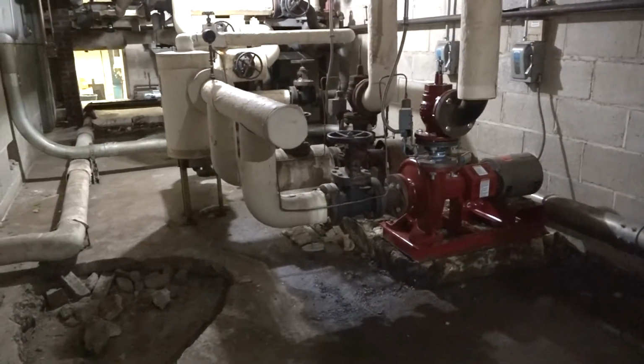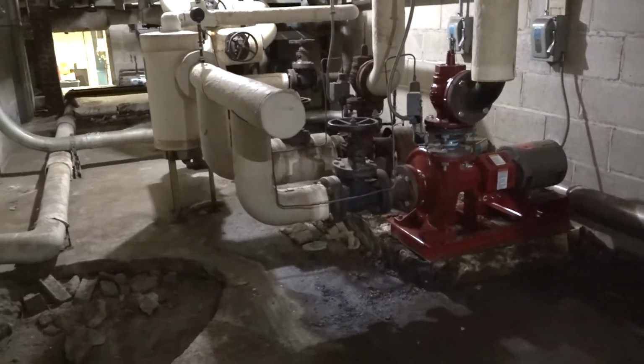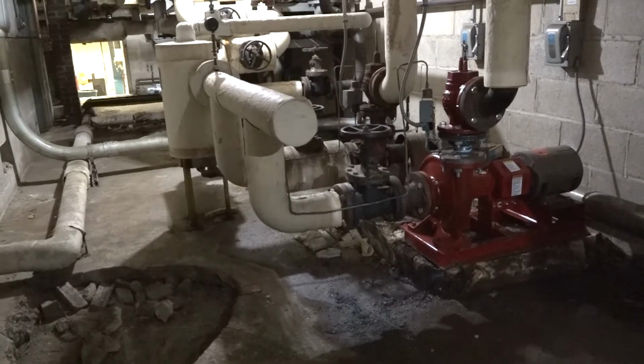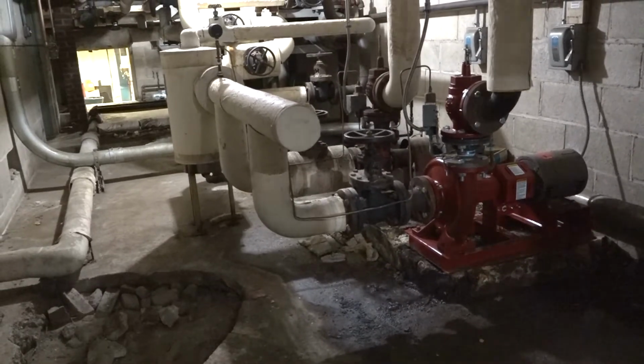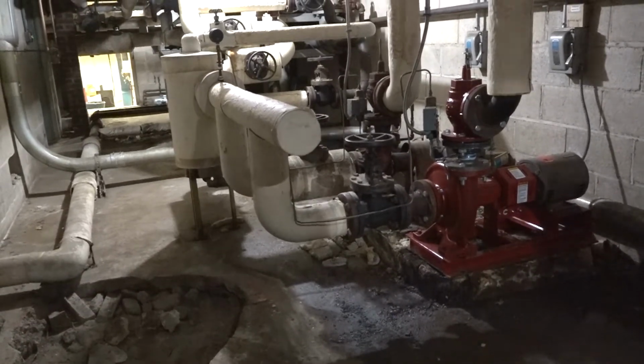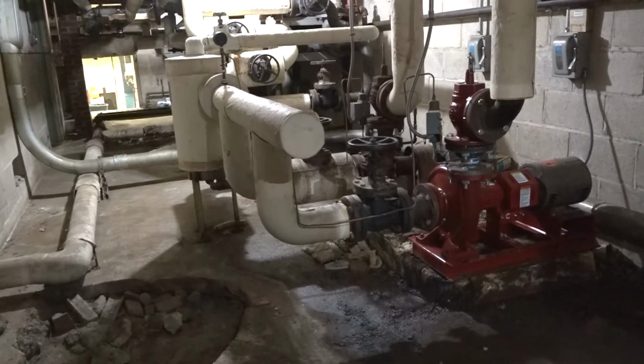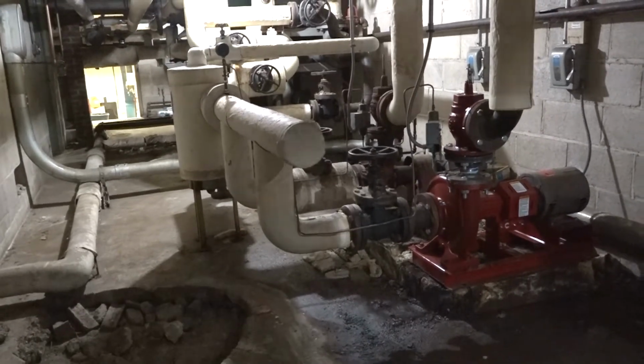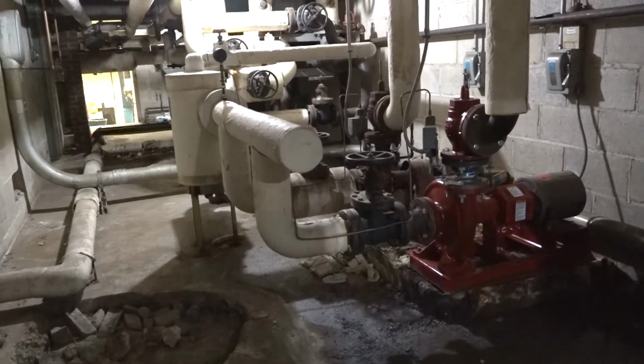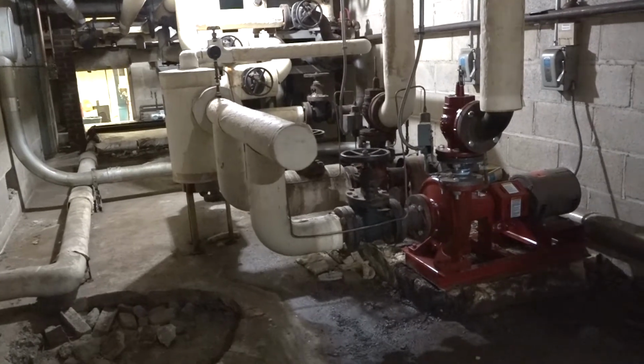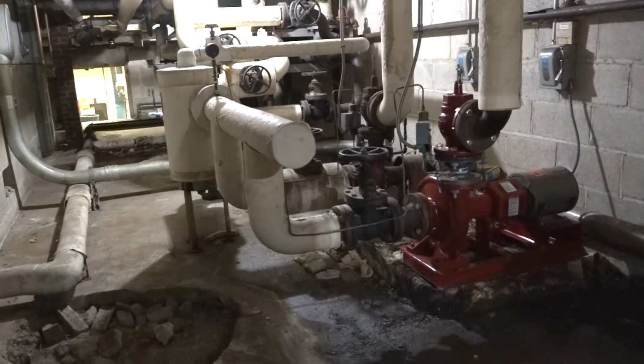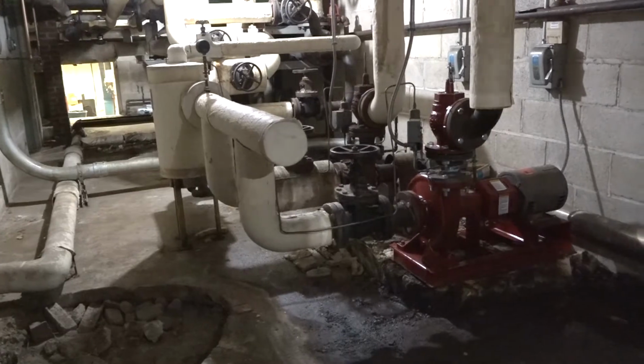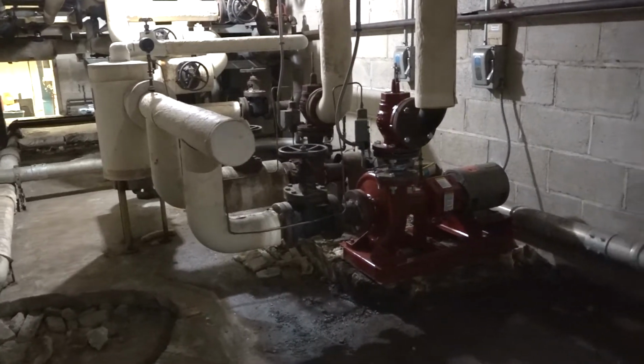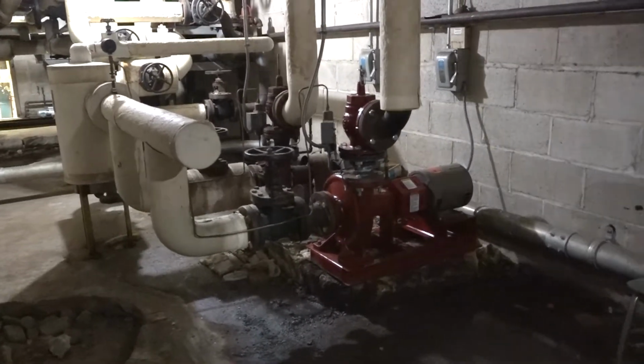So these are the circ pumps that come off of the heat exchanger, which is behind all the piping over there. The steam comes up in the heat exchanger, converts the steam into hot water through a city water feed, and then these pumps pump it through to the newer additions in the building. We had one pump fail 2 years ago. We had to replace the whole thing, base and all. Obviously, we reused the motor because that was still good.